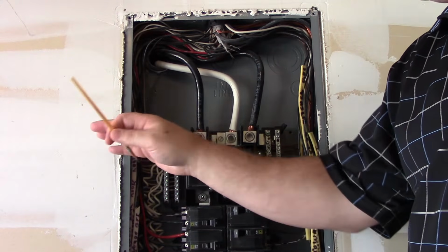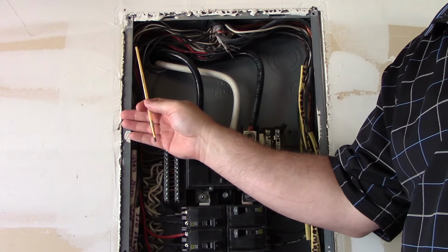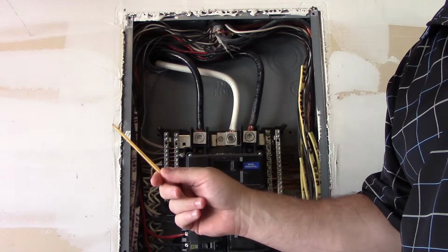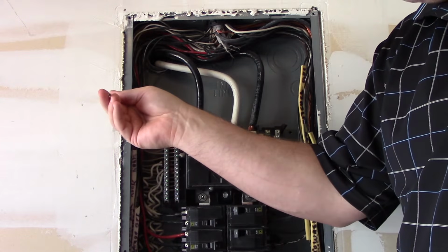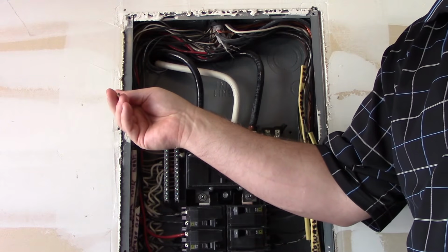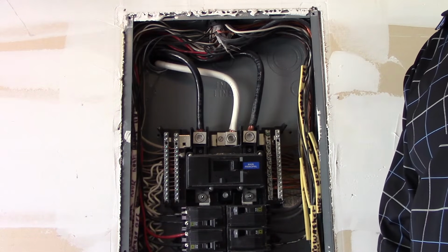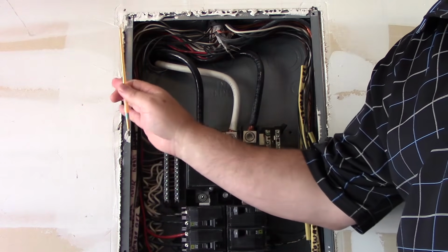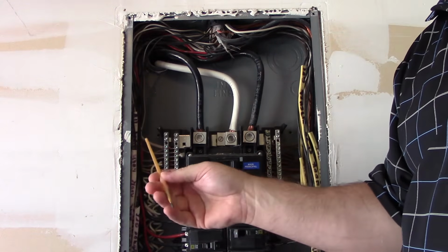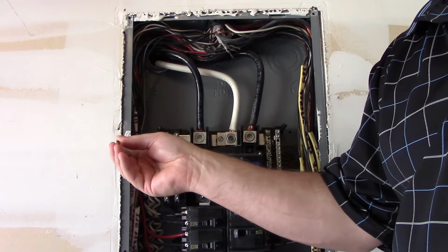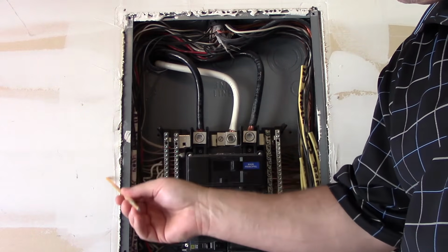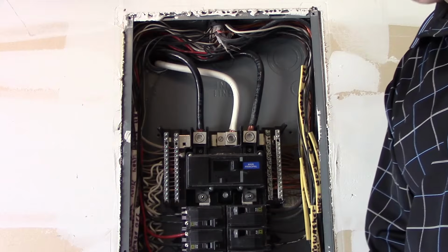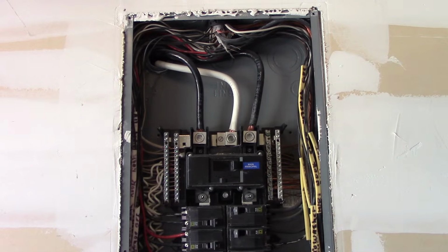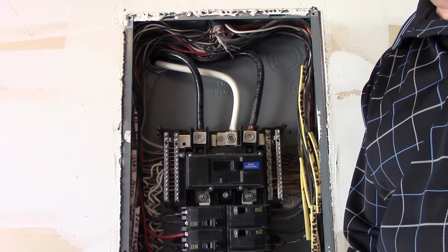Now, home inspectors, again, you also want to make sure this panel, if it is a non-combustible material, is not more than 1/4 of an inch deep in here, because there are some things that we can do to correct that. We also want to make sure that this gap around it, in accordance with 312.4, is not more than 1/8 of an inch around it, which is very common when somebody does a flip or remodel, or they did a change out and they trimmed it very poorly around it and you got these big gaps. The last thing we want is to have an arc and an ember get in between this material and smolder down in between this combustible material, the wood framing that's behind here. So we want to look for those types of things. So again, that's 312.3 and 312.4 of the National Electrical Code.